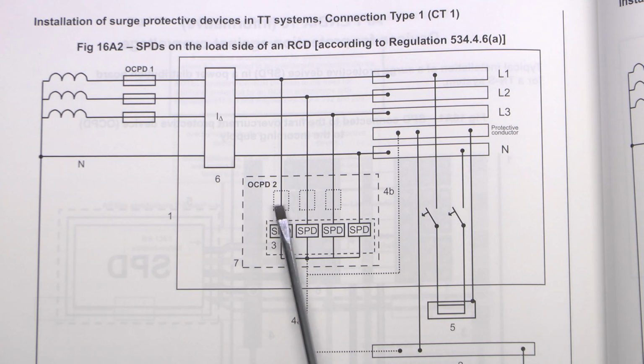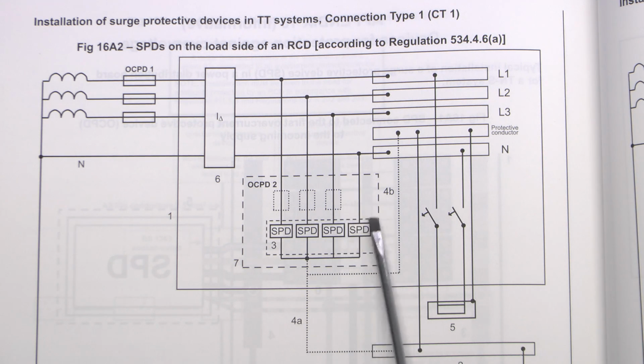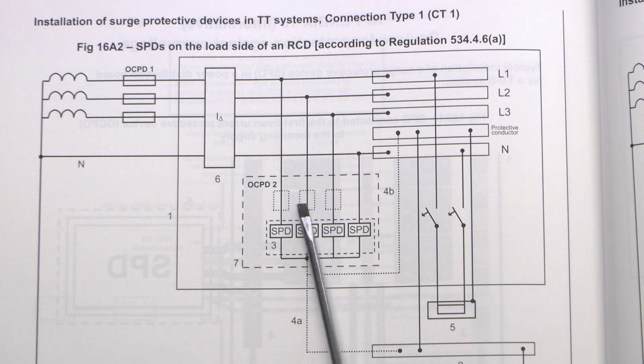So surge protective devices here, and then you have your overcurrent protective devices here if required. Previously on these diagrams these were shown as an option, but they were actually shown outside of the surge protective devices - two completely separate pieces. Now it's just shown as within the same assembly.